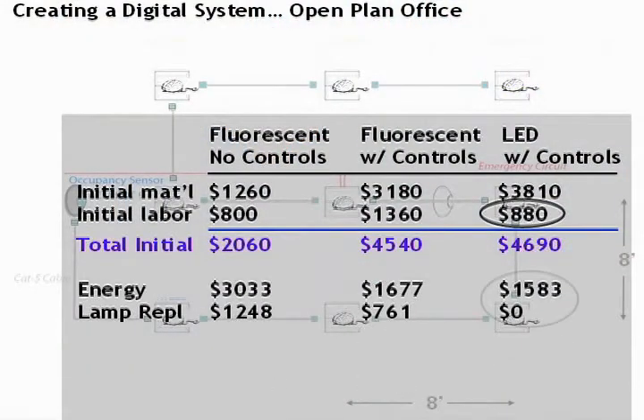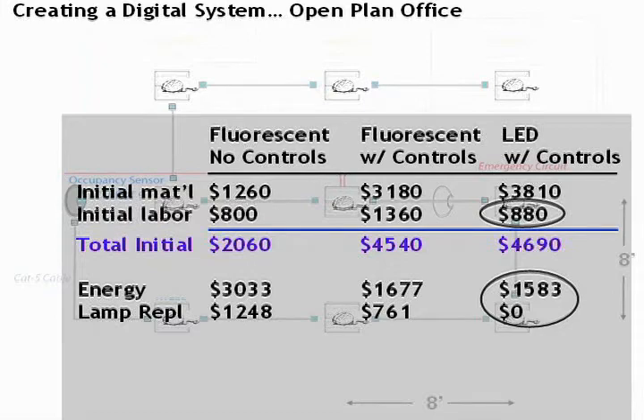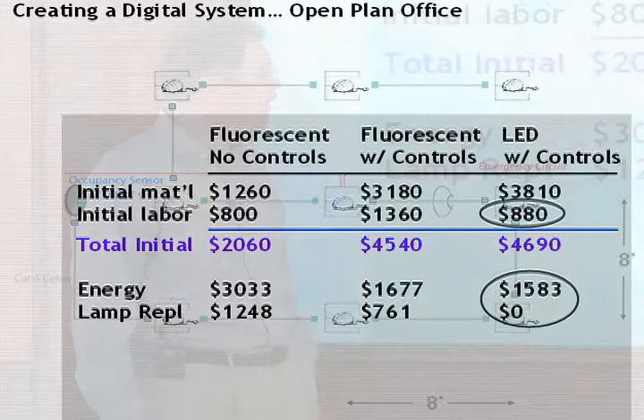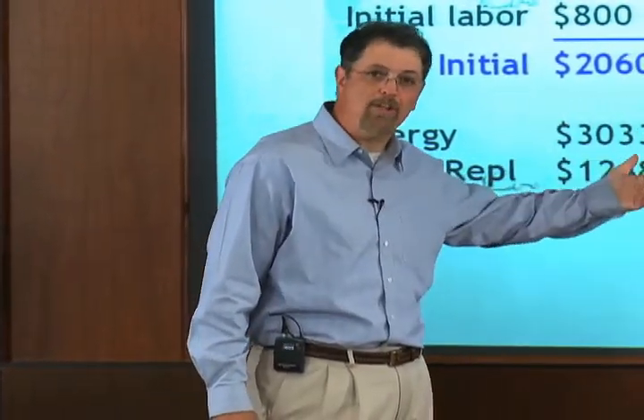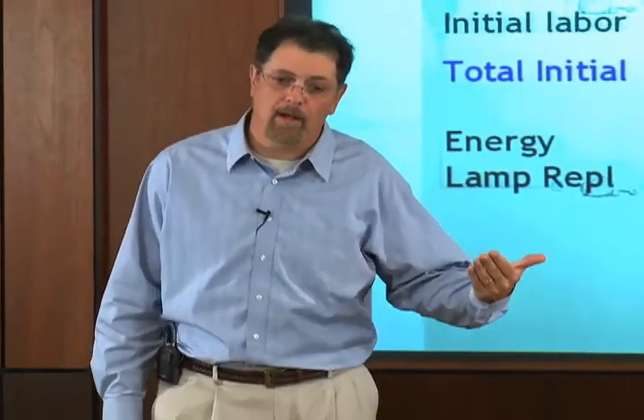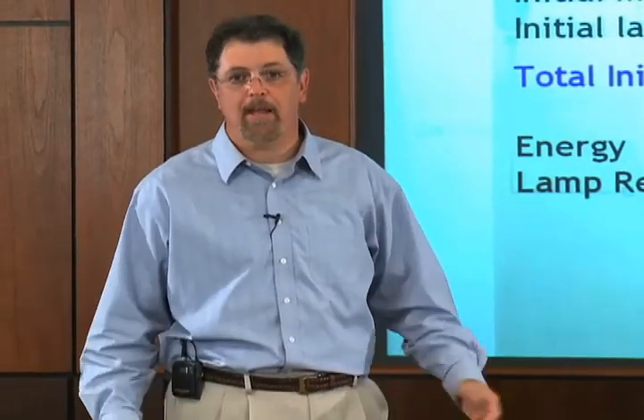If you bring that down to operating costs, you can see that the fluorescent system with no controls is very unfavorable in this comparison, in terms of increased energy cost and cost to replace the lamps. The performance of the fluorescent system with controls is really quite a bit better because the lamp life is going to be extended and energy consumption is reduced. But this comparison really weighs heavily in favor of the LED system with controls because of the additional energy savings and the absence of lamp change-outs and lamp maintenance.